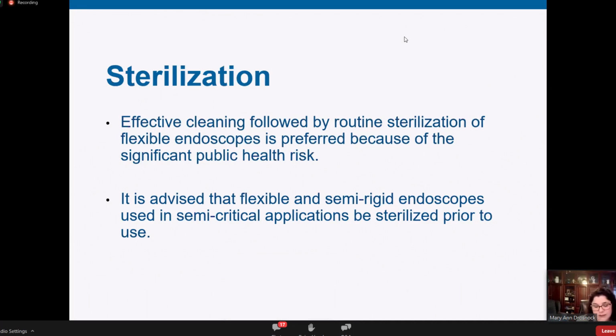You may be surprised. One of the first things I look at when I do audits of healthcare facilities is, what are you doing with your bronchoscopes? Most facilities don't think about it. They're putting them in the AER and going through high-level disinfection. Well, the vast majority of those types of endoscopes have been compatible with vaporized hydrogen peroxide systems for years. For 12 or 15 years or more, some of them have been compatible with systems like STERRAD and V-PRO certain cycles. So take a look at that.